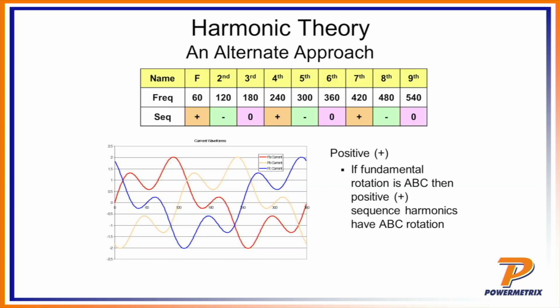What that means in terms of reality is, if I look at a positive harmonic, let's say we've got a 3-phase system, and its rotation is ABC, and we've got that hooked up to a 3-phase motor. A positive harmonic is actually going to try and push the motor to move a little faster. Those positive harmonics add up in such a way to induce the magnetic fields to run that motor a little faster than what it normally should be.